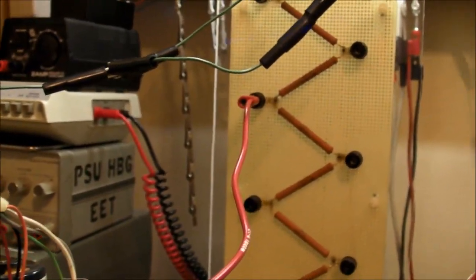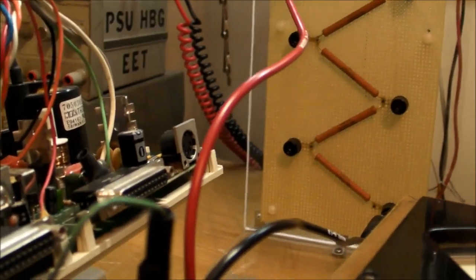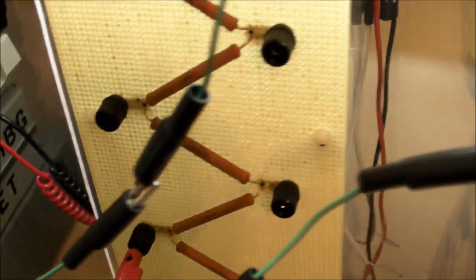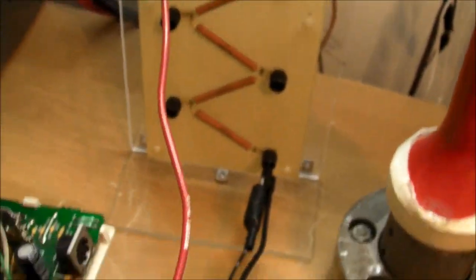Like I said, very important to maintain very wide distances between these. You can't really rely on the insulation because in most cases, like this Pomona model B12 good quality banana jack, that's only rated for 1000 volts I think. And of course this green insulation on these banana jack or alligator clip leads might be only 300 volt rating.